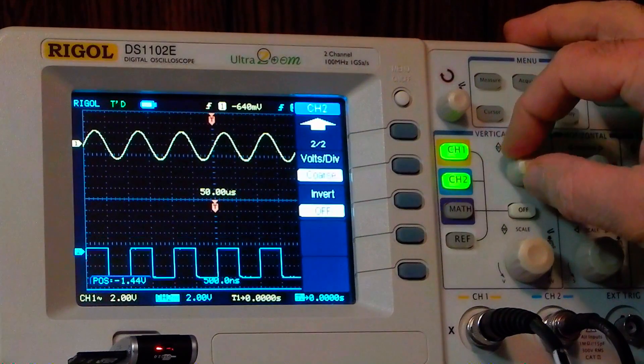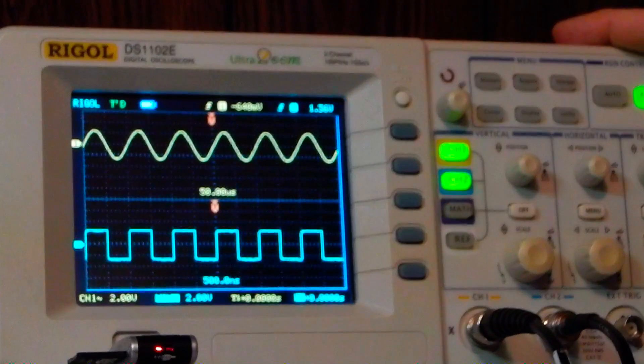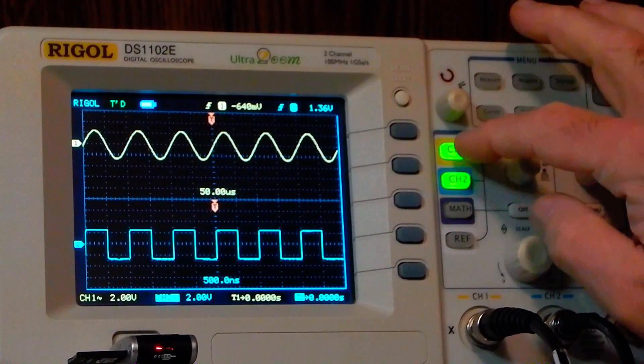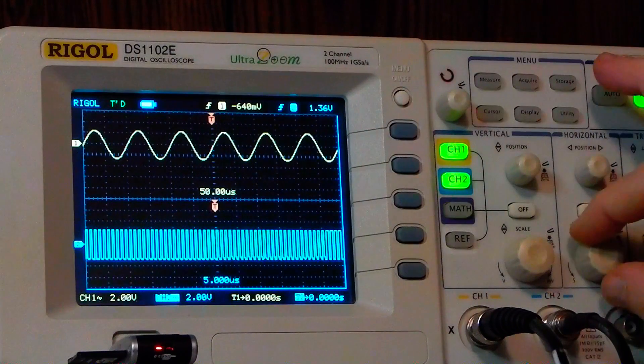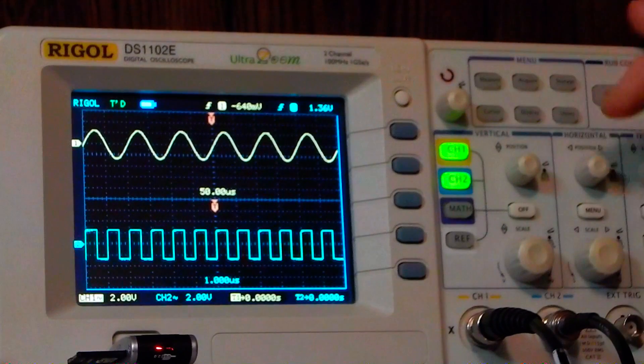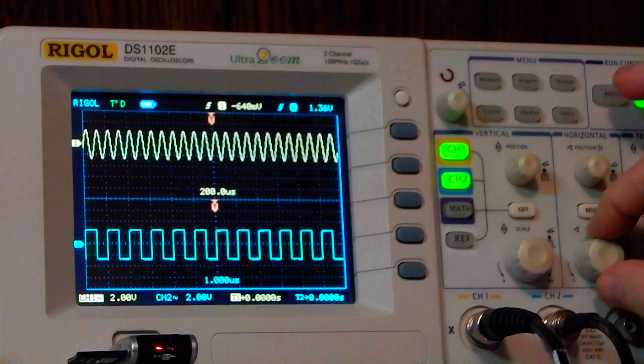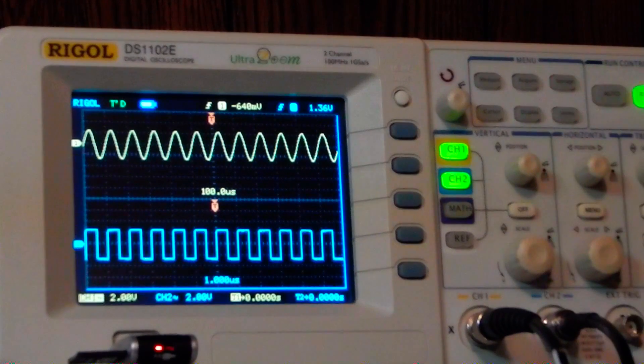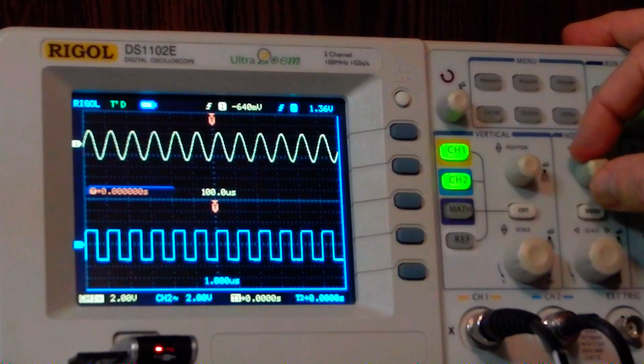The other thing is the horizontal time base. Depending which channel you're set to here, you can control the timing. Notice I'm adjusting the time base on the square wave but I'm not affecting the sine wave up here. Then I can just switch to channel one and do the same thing on the sine wave but not affect the square wave on channel two. They're independent of each other - all the settings are independent of each other, and that also includes the horizontal position and triggering point as well.